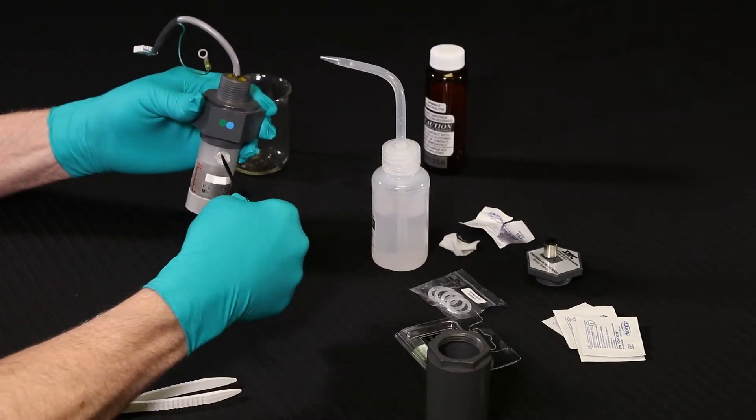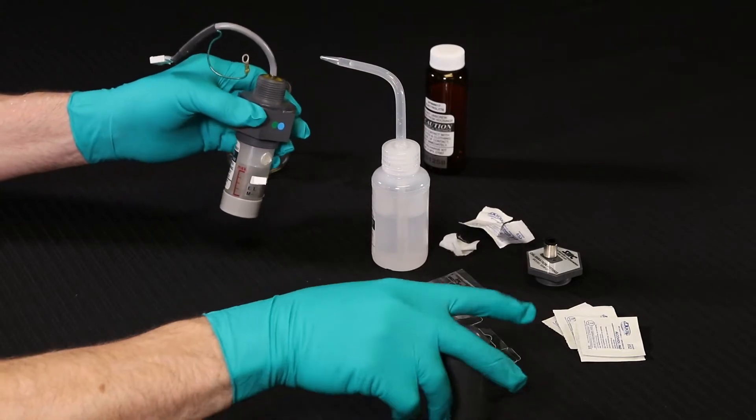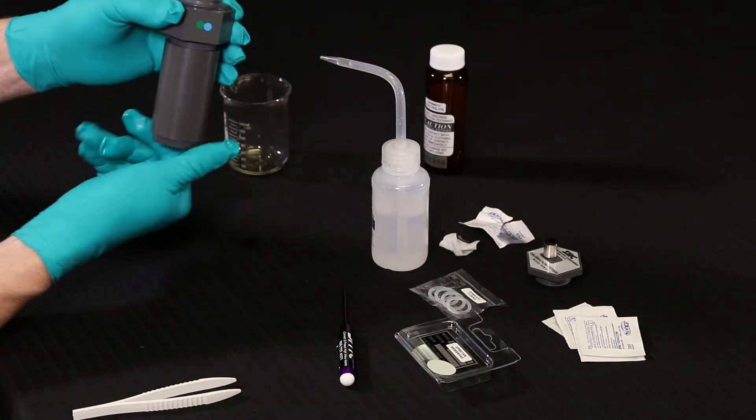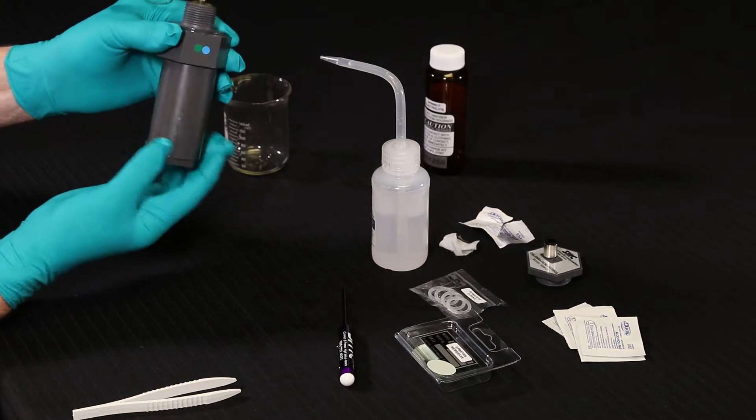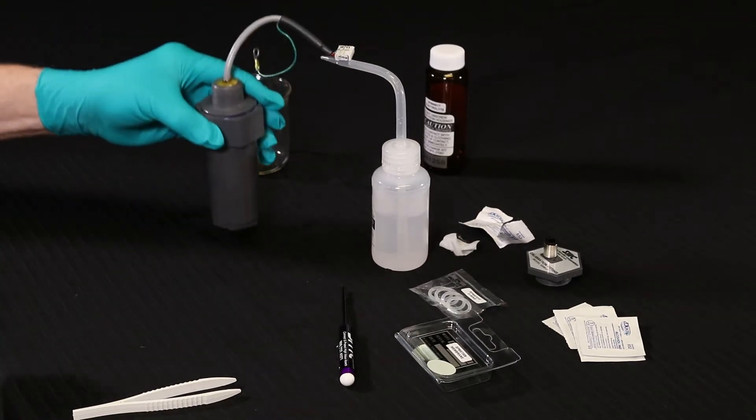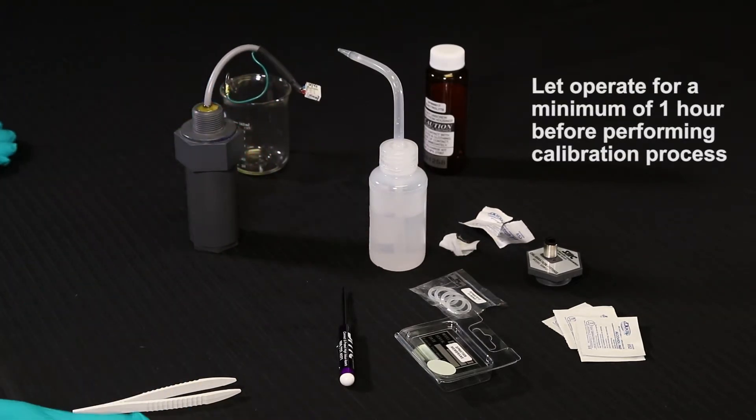This completes the sensor recharge process. Now, reinstall the sensor assembly into the instrument enclosure and plug the connector into the transmitter. Then, reinstall the gas detector to the proper location and replace power. Be sure to allow the new gas detector to operate for a minimum of one hour before performing calibration.